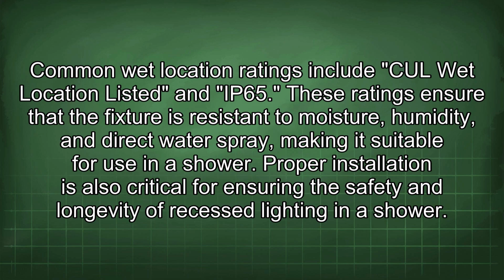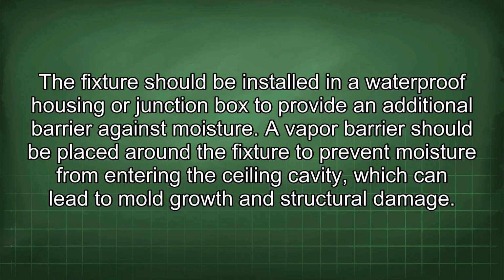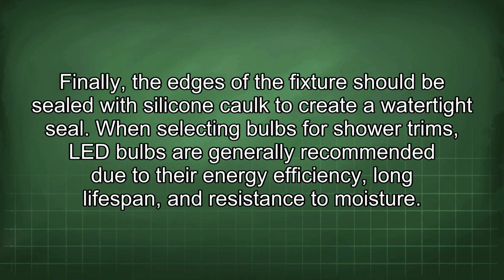in a shower. Proper installation is also critical for ensuring the safety and longevity of recessed lighting in a shower. The fixture should be installed in a waterproof housing or junction box to provide an additional barrier against moisture. A vapor barrier should be placed around the fixture to prevent moisture from entering the ceiling cavity, which can lead to mold growth and structural damage. Finally, the edges of the fixture should be sealed with silicone caulk to create a watertight seal.